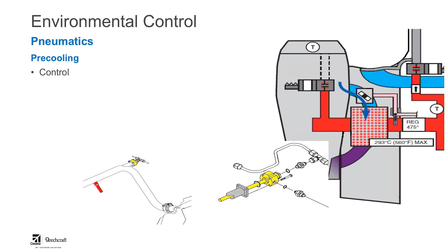So how do we control that? Well, we have a bimetallic pneumatic temperature probe that is in stream, downstream of the pre-cooler outlet. If you're looking at the image on the left, the bottom right corner there is the outlet of the pre-cooler. The bleed air tubing goes inboard towards the center of the aircraft in the tail cone and then makes a 90-degree turn forward.